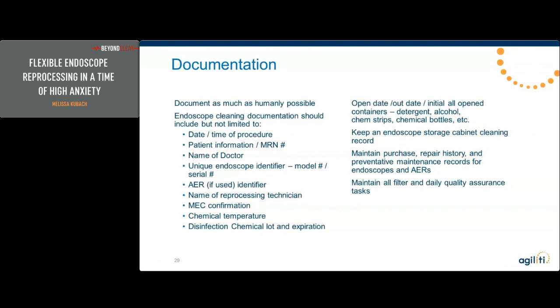Basically with these items, you cannot do anything but destroy them. You cannot reuse them, you cannot save them, and at least in this country, you cannot clean them. Since they did not keep track of their serial number, they had to incinerate all of their bronchoscopes, even the models that they knew there was no way they could have, would have ever used on him. It didn't matter. They had to, because that endoscope went back into the cabinet, everything it touched, they lost the reprocessing unit. They lost everything in that department, and it was devastating.